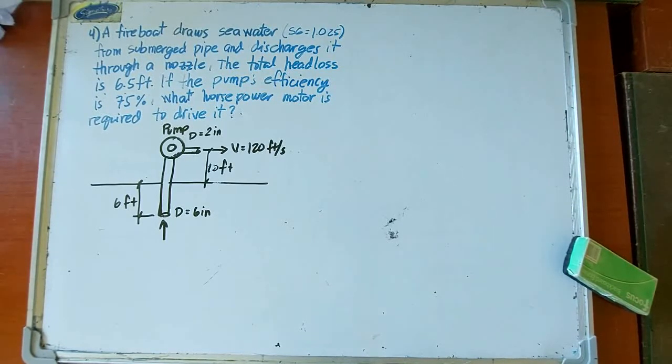We're going to apply the energy equation, Bernoulli's energy equation with a pump. So what are we going to do? We choose two points. When we apply the energy equation, we always need two points. In designating those two points, we need to consider that it should eliminate the number of unknowns in the equation. Another thing to consider is the direction of flow.